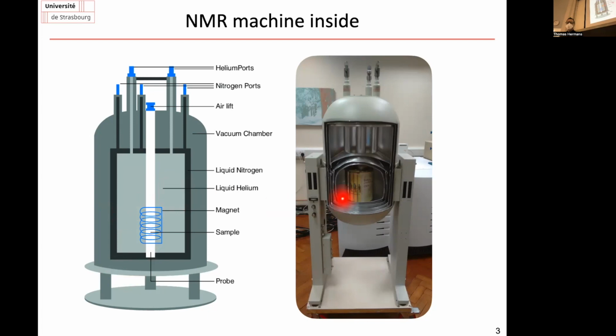Okay, so to lower this cost a little bit, they have different shells, and in a more outer shell, they will put liquid nitrogen, which is cheaper. So you use liquid nitrogen to keep cool the liquid helium, which cools the magnet. On top of that, there are these different layers, just like in a thermos can that you use for coffee. There's a little vacuum layer in between for insulation. Okay, so then here you have your magnet in liquid helium, liquid nitrogen around, everything is nice.